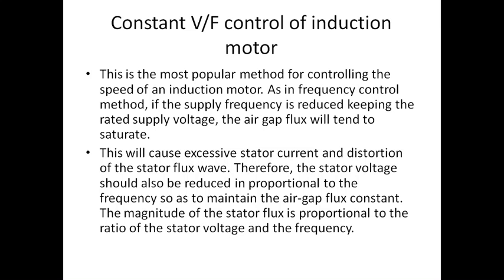Next is your constant voltage and frequency control of induction motor. If you give a constant voltage and frequency ratio, I'm going to control the speed of my induction motor. This is the popular method we are going to use. In the frequency control method, the supply frequency is reduced, keeping the rated supply voltage. The air gap flux then tends to saturate. I'm going to give the rated supply, meaning input voltage, in a proper manner. The speed control is totally with your torque equation. According to how my torque equation behaves, I control the speed of my particular motor.